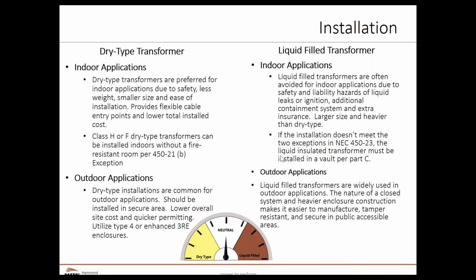Installation is probably one of the biggest concerns when somebody comes and says, hey, let's look at options. I have a liquid filled transformer. I want to look for options with a dry type transformer. And the issue here is that the transformers really are installed differently. For indoor applications, there isn't a lot of additional prep work that we need to do with a dry type transformer if it's going into a standard electrical room.